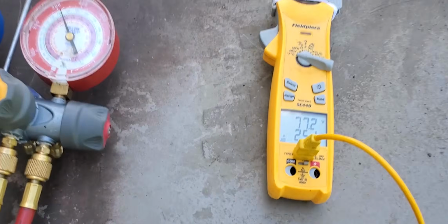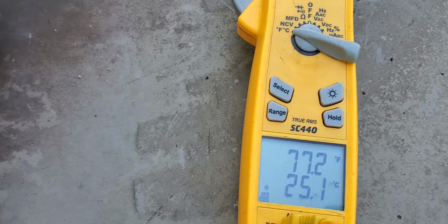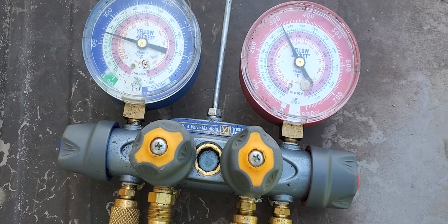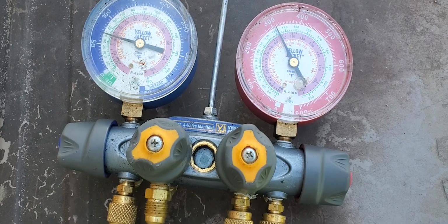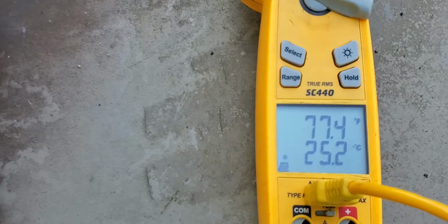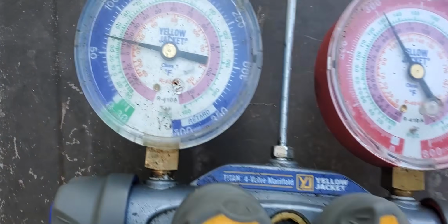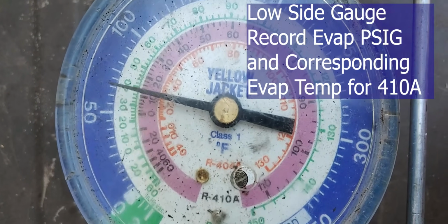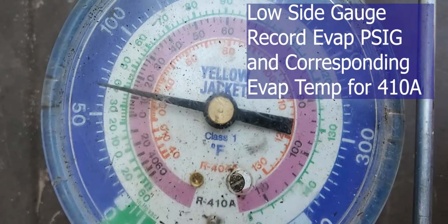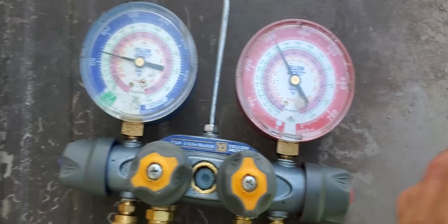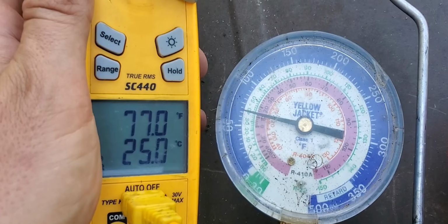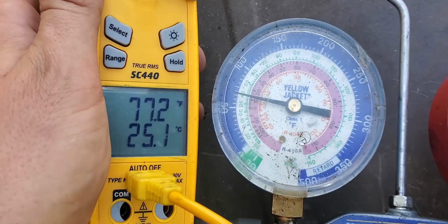So we want to make sure that we have a good method to check refrigerant charge. Today, I want to show you what tools you need, and I want to show you the method I use. There are a number of ways to determine if the refrigeration system has the right amount of refrigerant. What I would like to talk about today is subcooling and superheat. Today, I want to check charge by subcooling and superheat.